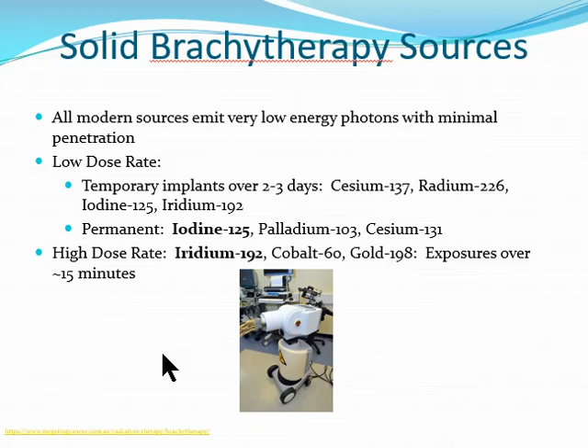If permanent, it just stays inside of the patient permanently, although because of radioactive decay it becomes essentially inert after a period of time. With our HDR unit, inside of here is where the source is normally, but if we have the patient in the room and whatever applicator is inside of the patient connected to catheters that connect to this, then when everyone leaves the room, the source will go out of here, in through the catheter, into the patient for like 15 minutes.